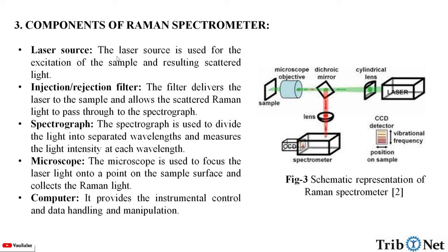The main components of the Raman spectrometer are: the laser source, which is used for the excitation of the sample; the injection or rejection filter, which delivers the laser to the sample and allows the scattered Raman light to pass through; the spectrograph, which divides the light into separated wavelengths and measures the light intensity at each wavelength; the microscope, which focuses the laser light onto a point on the sample surface and collects the Raman light; and the computer, which provides instrumental control and data handling and manipulation.